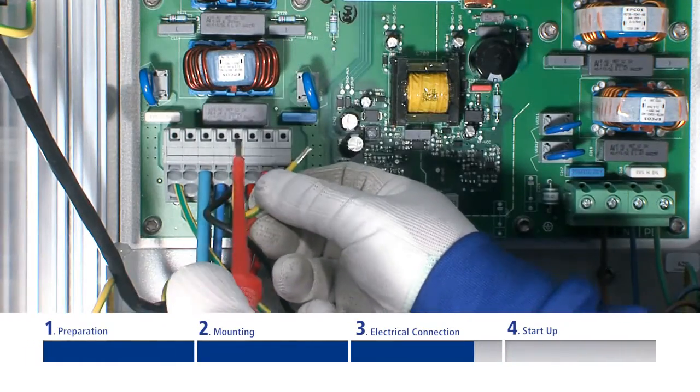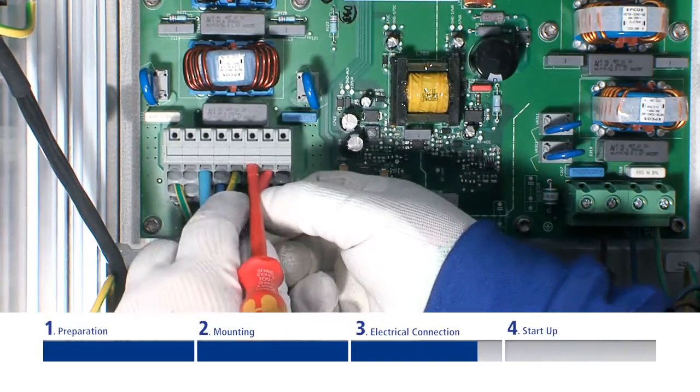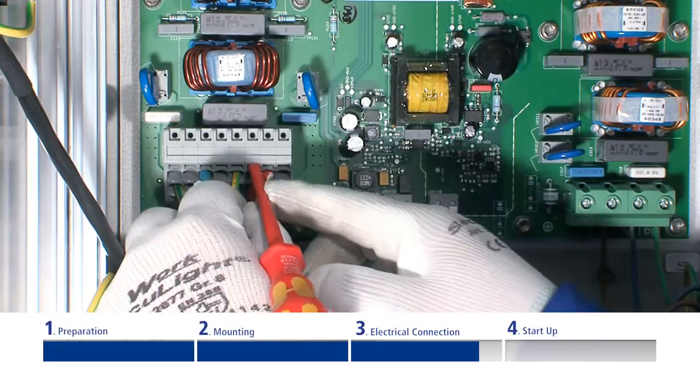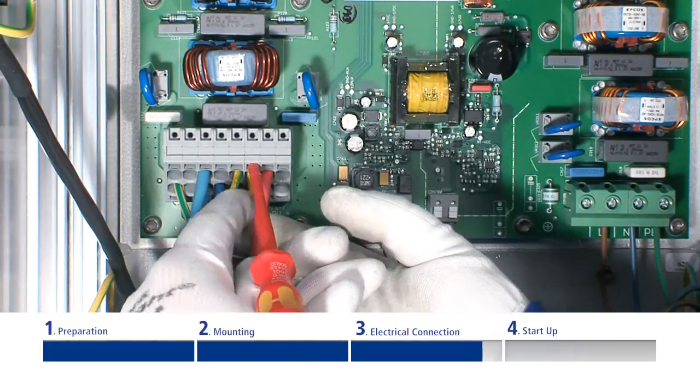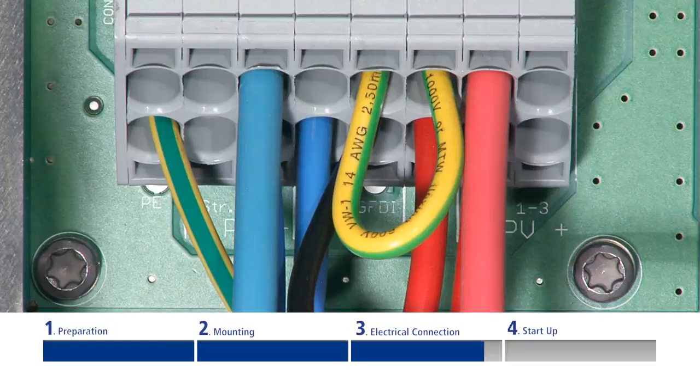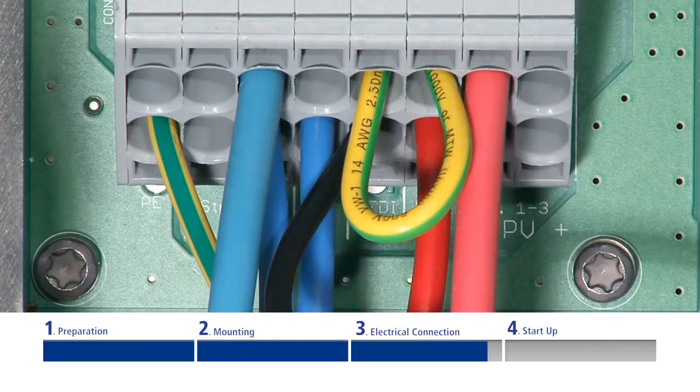Clamp the enclosed cable bridge in the upper GFDI terminal and the DC plus or DC minus terminals depending on whether positive or negative earthing is required. Earthing monitoring is to be activated after startup via the display.